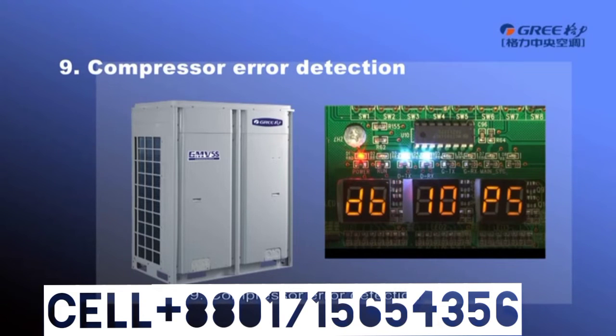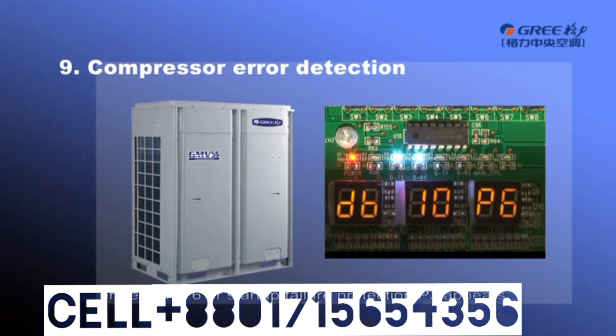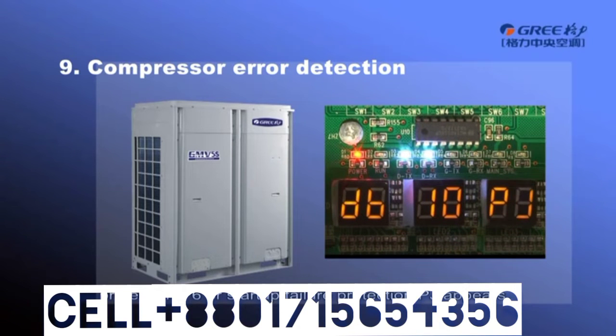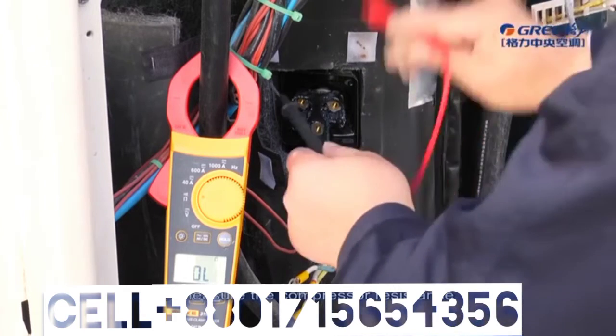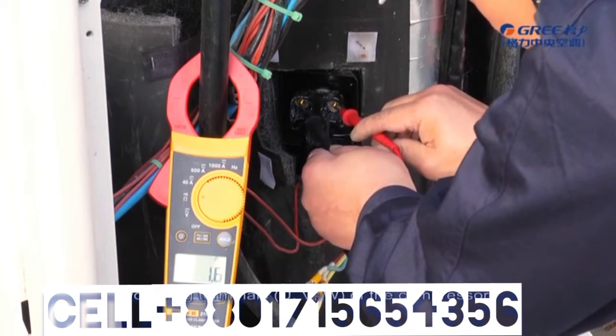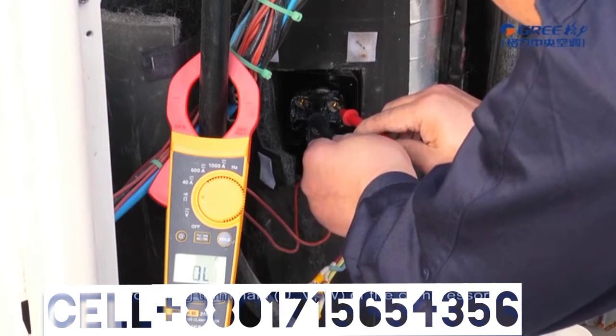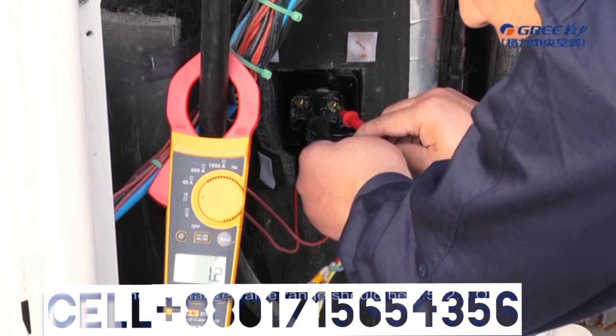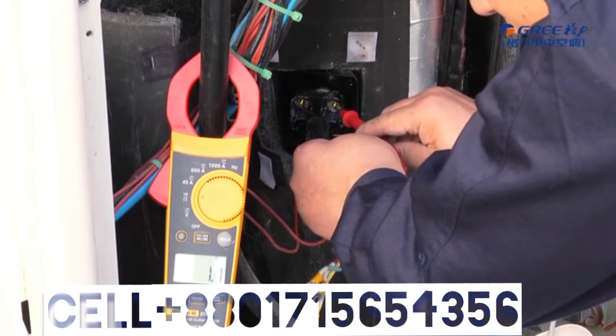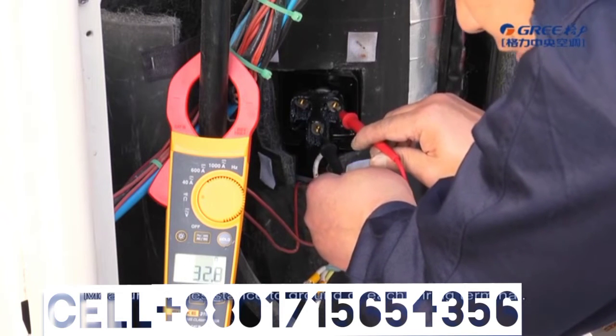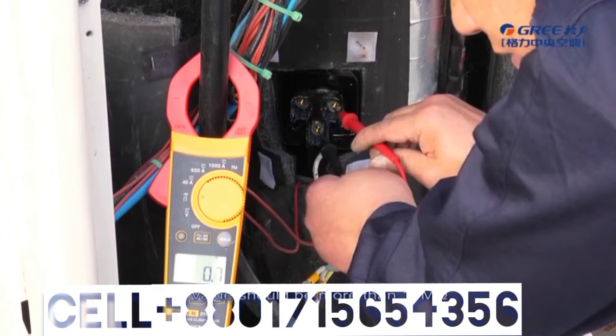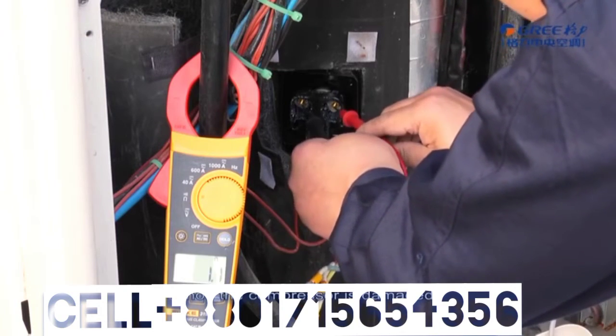9. Compressor error detection. When the compressor overcurrent protection P5, IPM module protection P6, or startup failure protection PJ appears, please confirm whether it is an anomaly of the compressor or an anomaly of the IPM module. The confirmation methods are as follows. First, measure the compressor resistance. Measure the resistance between two wiring terminals, U, V, W, of the compressor. The resistance value range should be 0.5 to 2.0 ohm. Measure the resistance to ground of each wiring terminal. The value should be more than 10 megaohm. If not, the compressor is damaged.